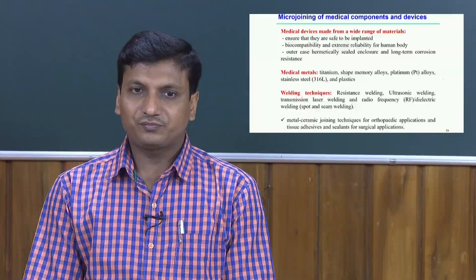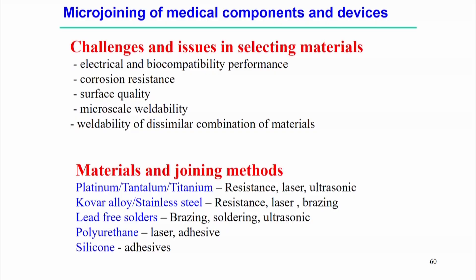What are the typical challenges and issues in selecting materials for the micro joining of medical components and devices? First, bio-compatibility performance as well as electrical conductivity is sometimes required. Corrosion resistance and surface quality or surface finish should be very high even after welding, and micro-scale weldability of materials — most importantly the weldability of dissimilar combinations of materials — brings different challenges in micro joining applications.